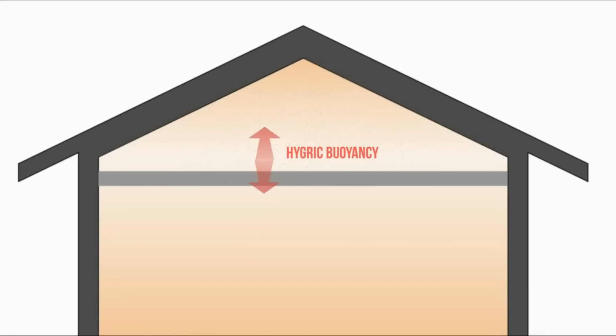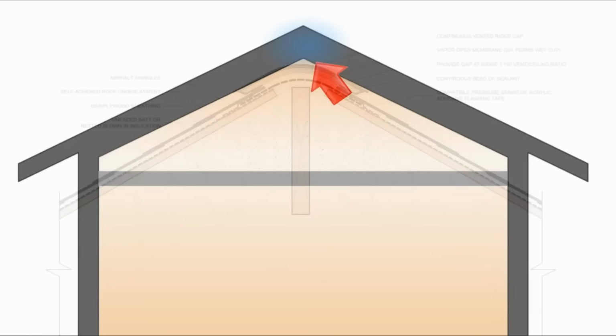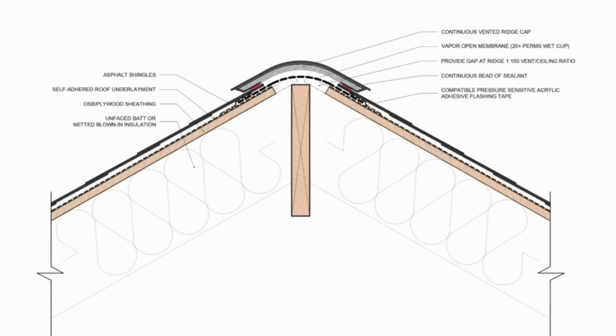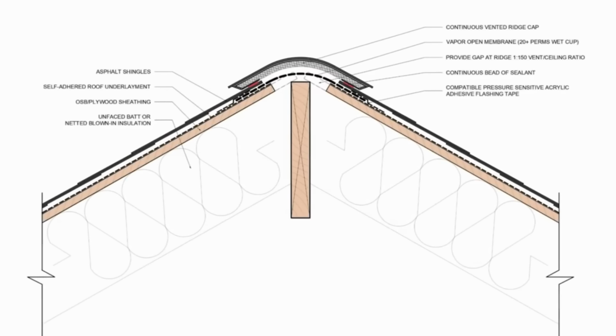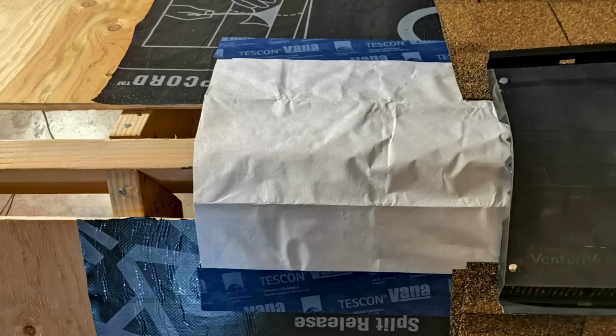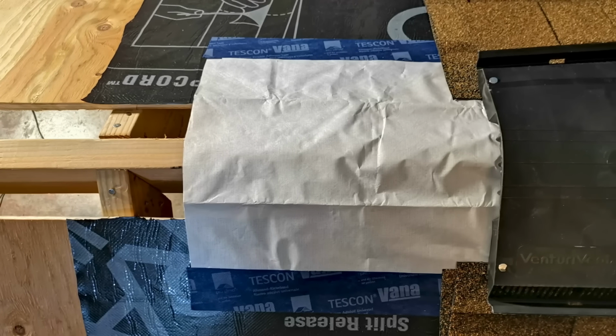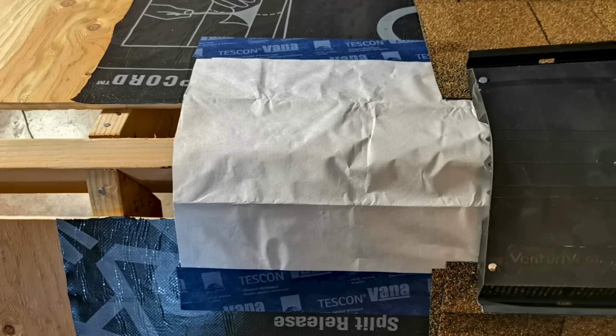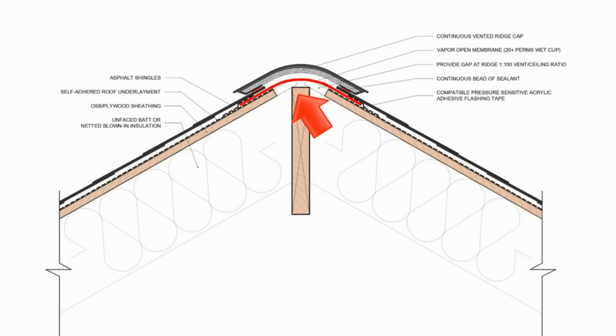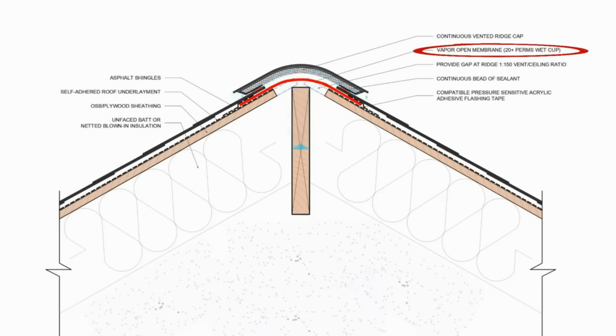To understand how this works, you have to understand hygric buoyancy. Warm, moisture-laden air is less dense than dry air, and will displace dry air, meaning water vapor naturally rises and accumulates at the highest point of the roof assembly, the ridge. To build a vapor diffusion port, you cut a slot in the roof sheathing at the ridge, identical to a standard ridge vent condition, but instead of leaving it open, you seal that slot with a watertight, airtight, but highly vapor-permeable membrane that has a perm rating of around 20 perms. This membrane maintains your continuous air barrier and keeps out rainwater, but allows the accumulated water vapor to passively diffuse out of the building. You then cap the ridge with a standard ridge vent to facilitate a small amount of airflow above the membrane to carry the moisture away.